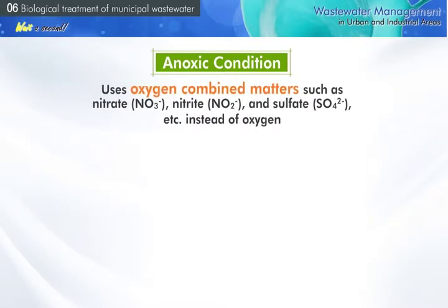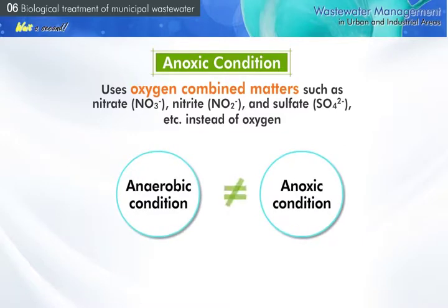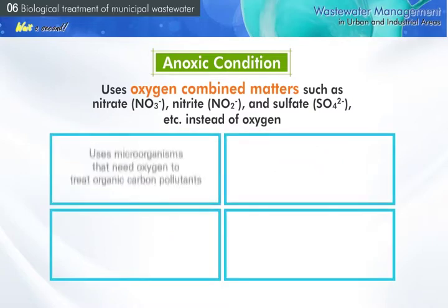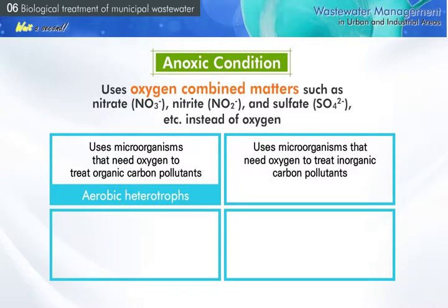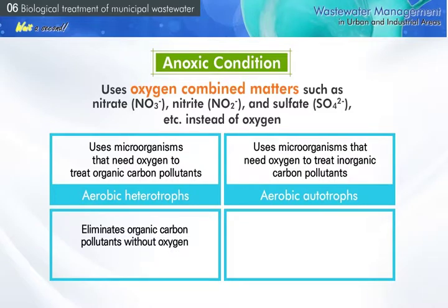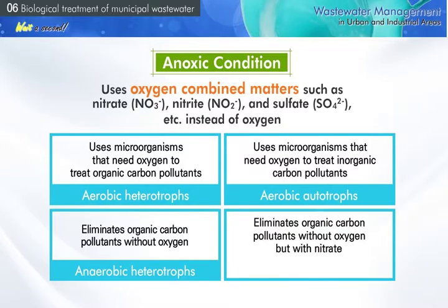Some anaerobic bacteria use matters combined with oxygen, like nitrate, nitrite, and sulfate, instead of oxygen. In wastewater treatment, this is called anoxic condition to distinguish it from anaerobic condition. For example, aerobic heterotrophs remove organic carbon pollutants needing oxygen; aerobic autotrophs treat inorganic pollutants needing oxygen; anaerobic heterotrophs treat organic carbon without oxygen supply; and anoxic heterotrophs use nitrate instead of oxygen to treat organic carbon.